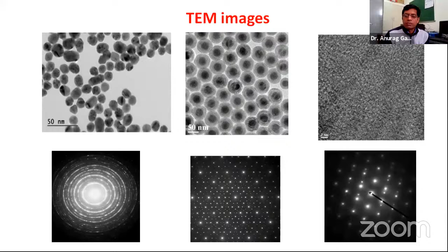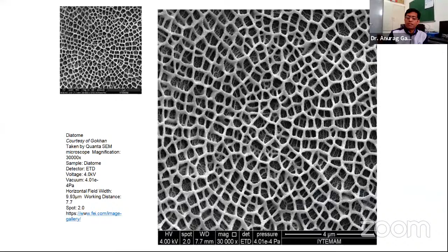This is again an image from scanning electron microscopy. It's again a porous material. So you can calculate the pore size. And again, there is information. High voltage is 4 kV, spot size is 2, the distance from the detector is 7.7 mm, magnification 30,000 times, and pressure, that is the pressure inside the column, meaning the vacuum. So the surface morphology structure you can get from scanning electron microscopy images with the help of this.